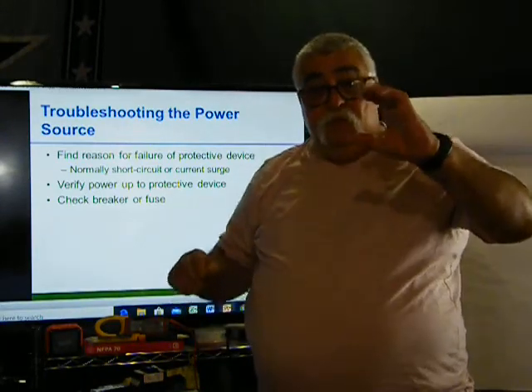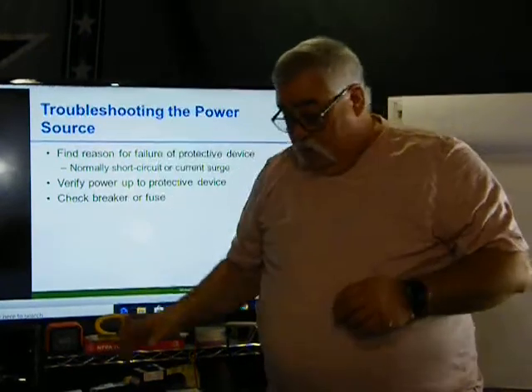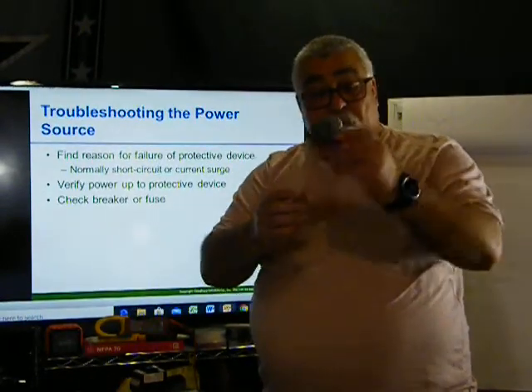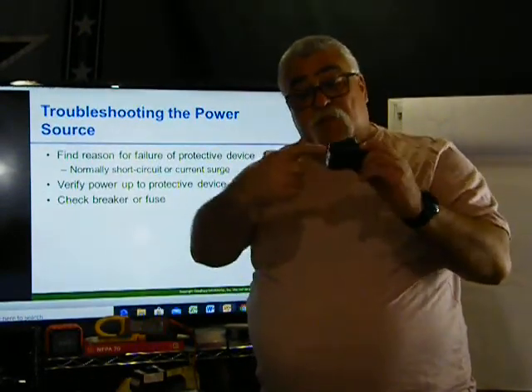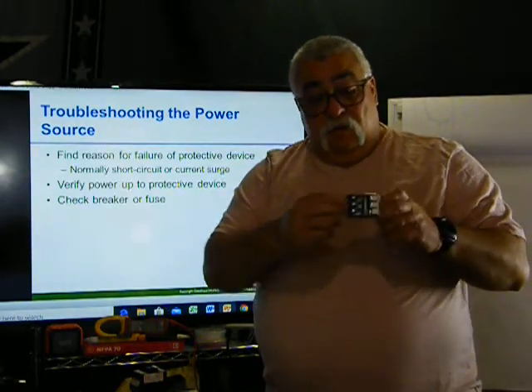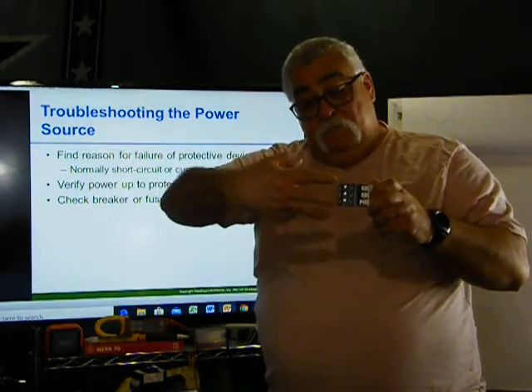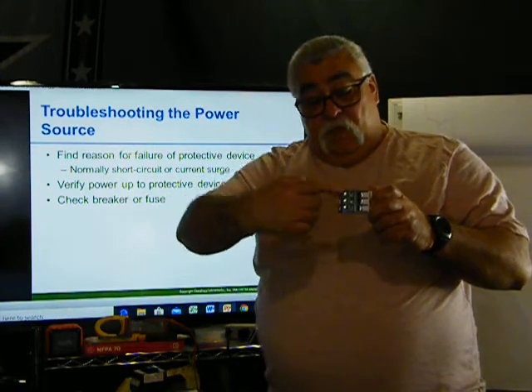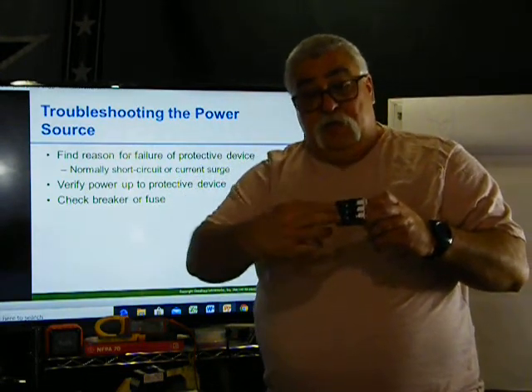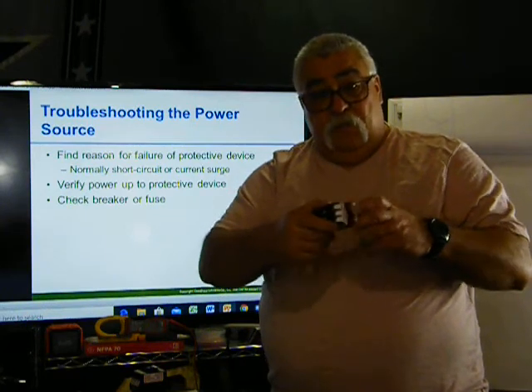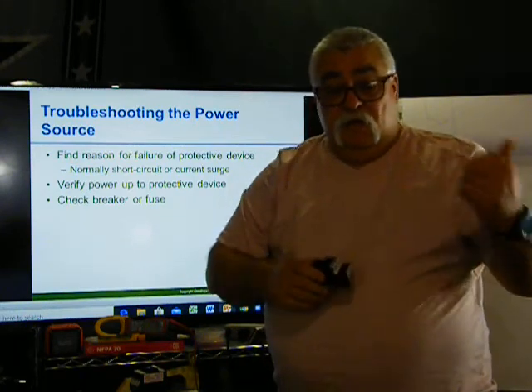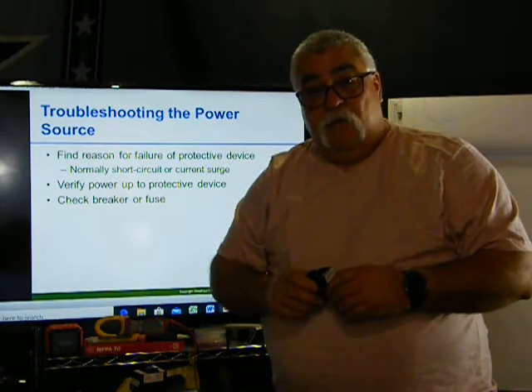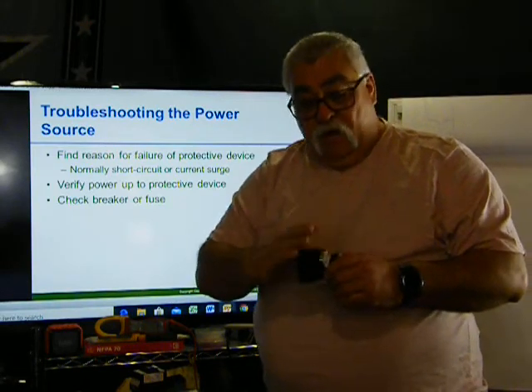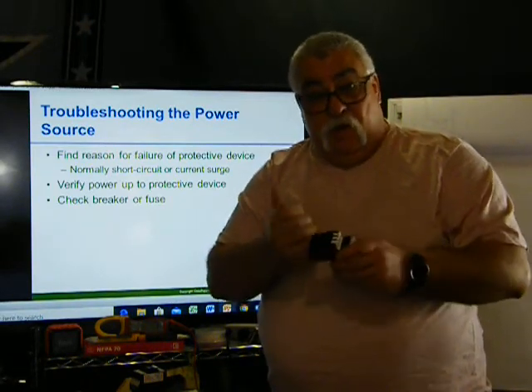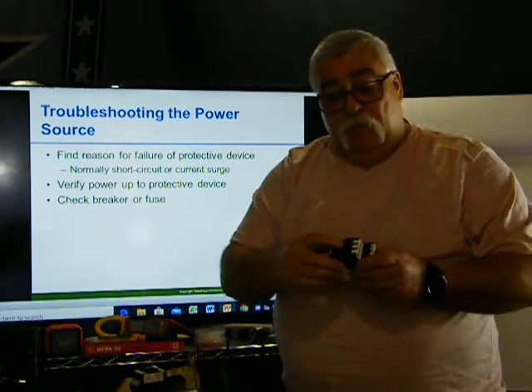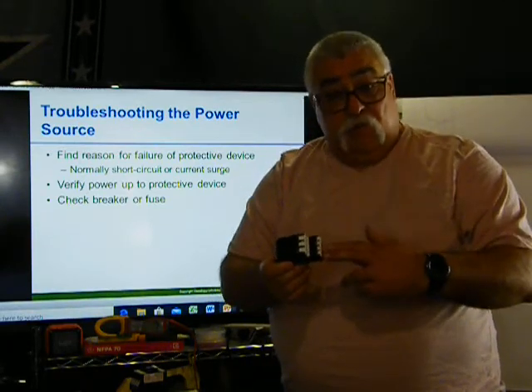So you go to the breaker and check. I don't have one with me, but my breaker is bolted on this side, and this is where my wires go out that way. Here's where the wires come in. I check here: the breaker's in the on position. I check here, and this says no power. Guess what? I want to check on the source. Make sure the source is hot. You want to verify that this has power coming into it and power going out of it. Even with the breaker off, you can't check it on the outside, but you want to make sure power is coming in.